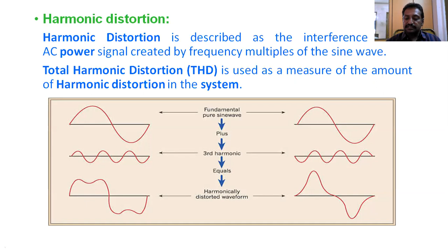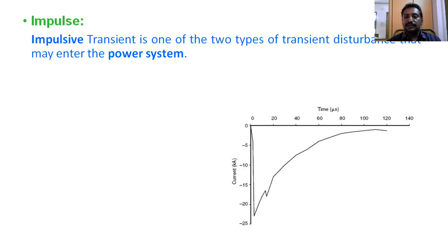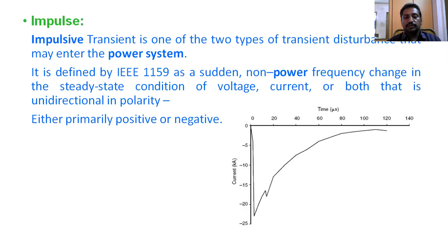Impulse. An impulse means a sudden increase in the voltage for a short span of time, at an instant. It is also called a transient, one of the two types of transient disturbances that may enter the power system. As per IEEE 1159, it is a non-power frequency change in the steady state condition of voltage, current, or both, that is of unidirectional polarity. Generally there are two types of impulses, either positive impulse or negative impulse.